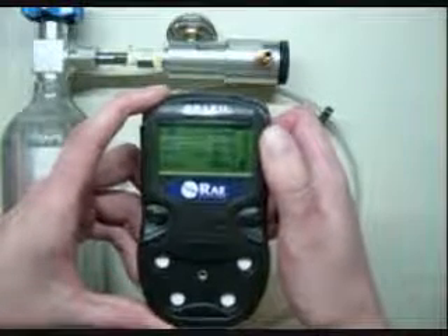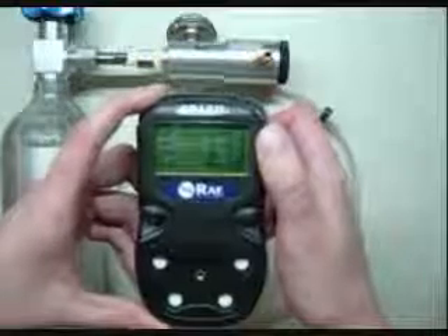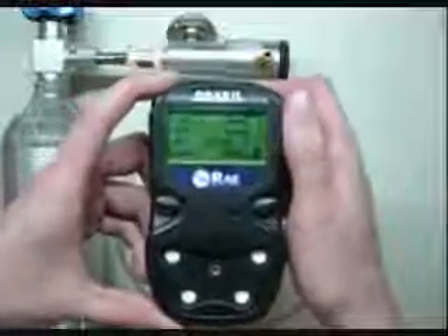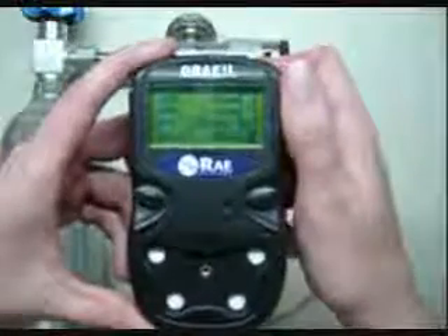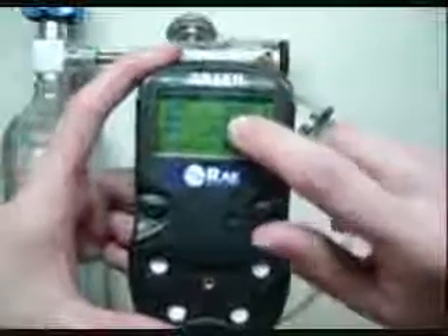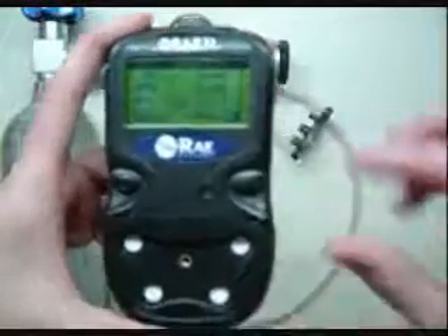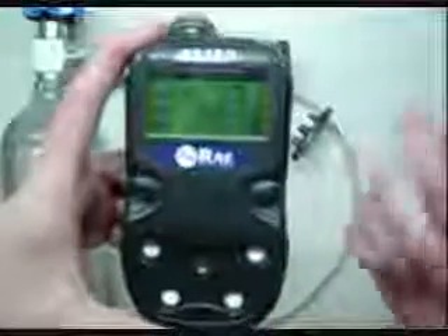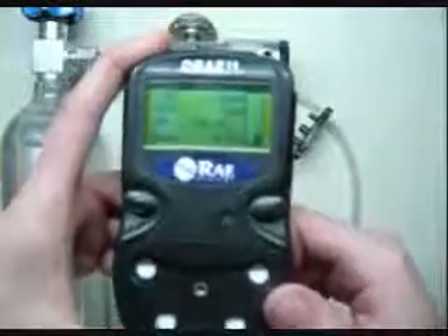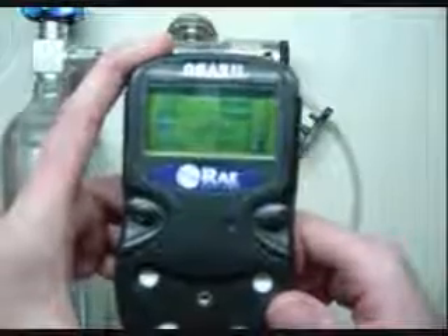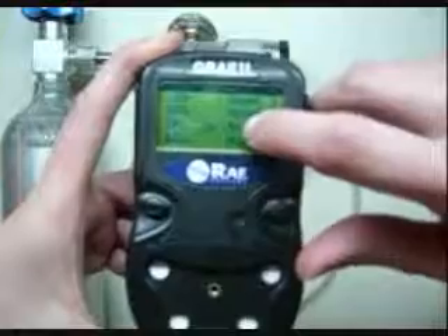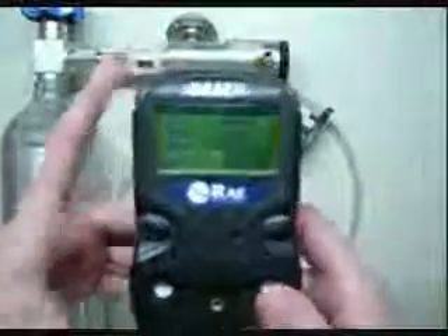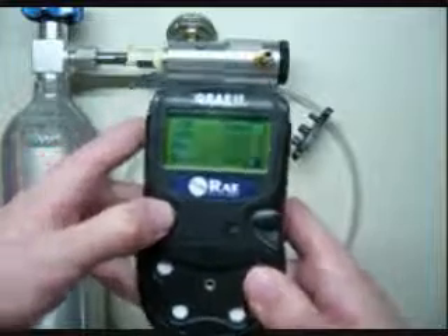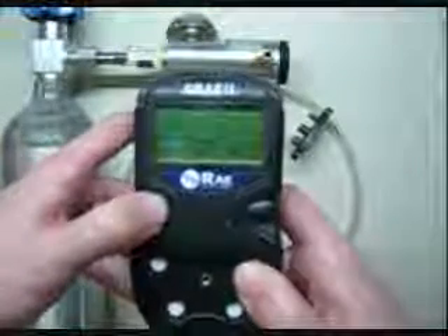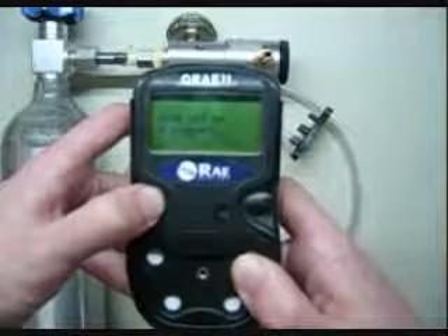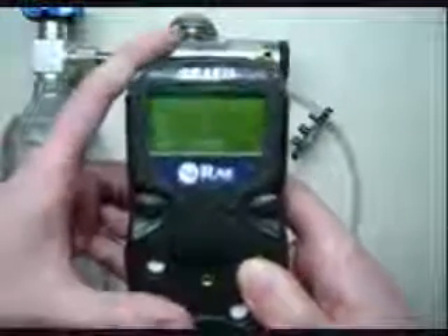Okay. Notice it does take a little while for the numbers to fall here. You can see that the carbon monoxide is still at 2 parts per million. What's actually happening is there's a little sensor in there that's chemically removing the gas and changing it into electricity like a little battery. Okay, there you go. Now we're back at 0, 0, 20.9 for oxygen, and 0 for LEL. So we can turn the unit off, hold the button on the left, it'll beep once. 4, 3, 2, 1, and you're all set.